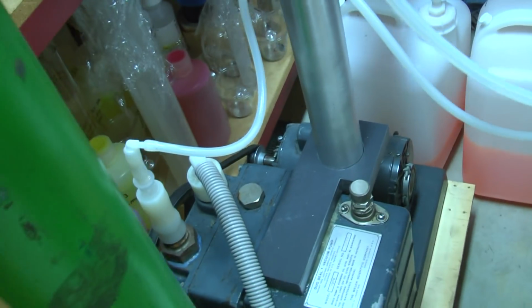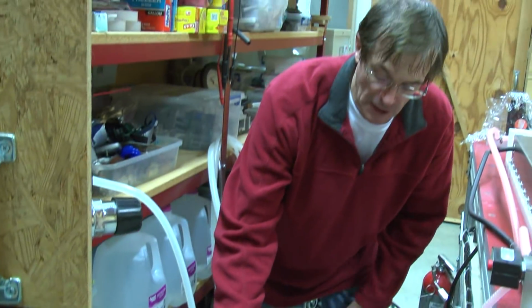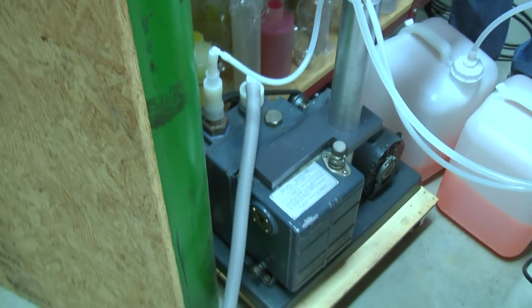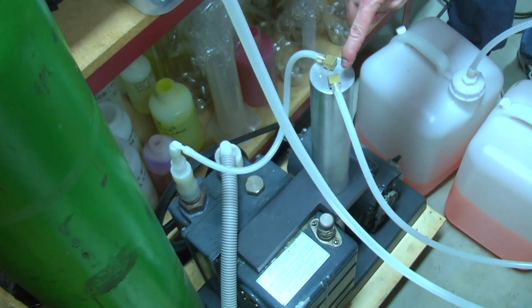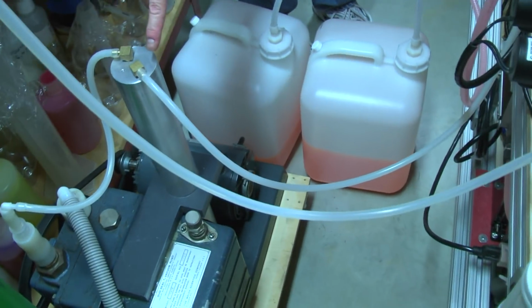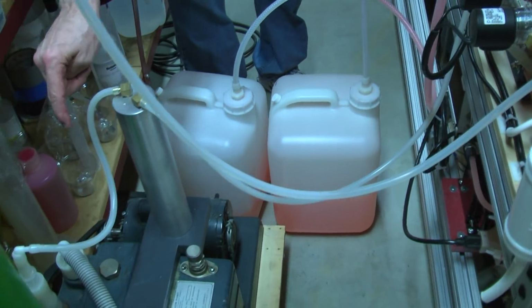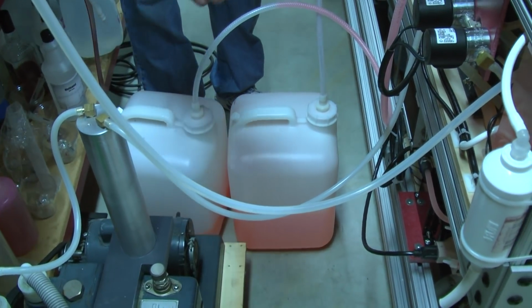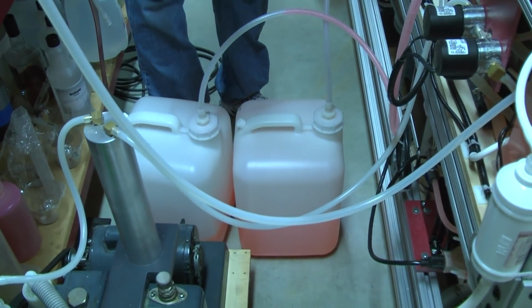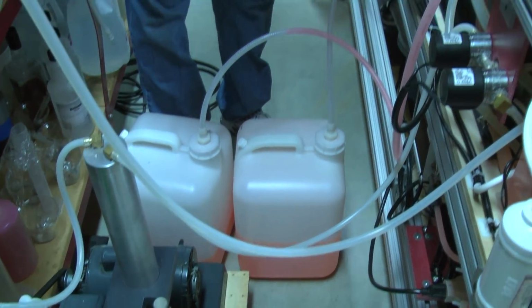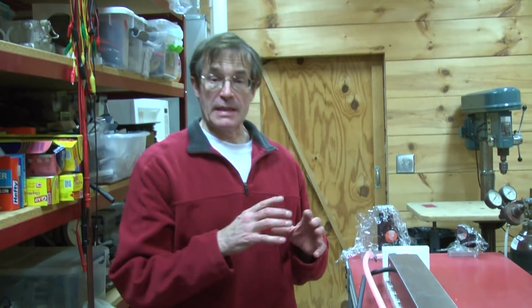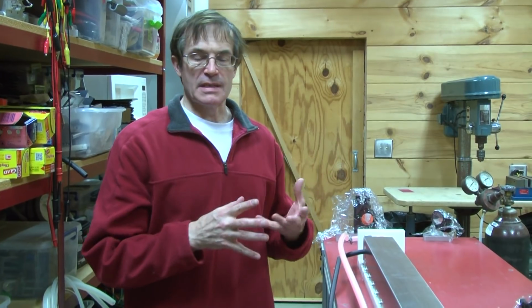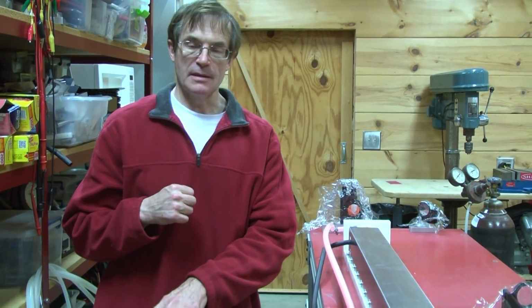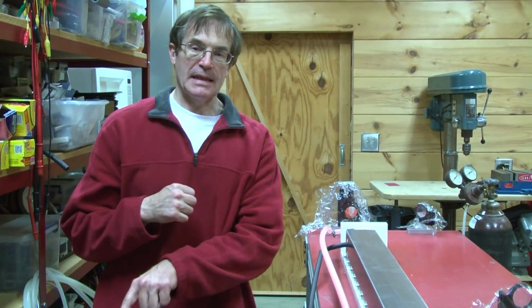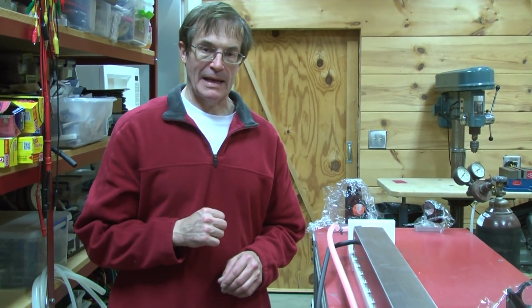The reason for this is twofold. One is during the periodic dumping and filling, the vacuum pump continues to run and draws this down to a moderately high vacuum. So when the valve opens, the flow of gas out of here is very rapid because it doesn't depend on the real-time pumping rate of the vacuum pump. And so you get a much quicker discharge, or essentially a much quicker triggering. And then finally, if there was a catastrophic explosion that occurred, as I keep talking about in this video, then all the glass and the fluids and everything that might potentially get into the vacuum line will dump into that ballast or that chamber and not get into the vacuum pump. So it's a safety backup feature.